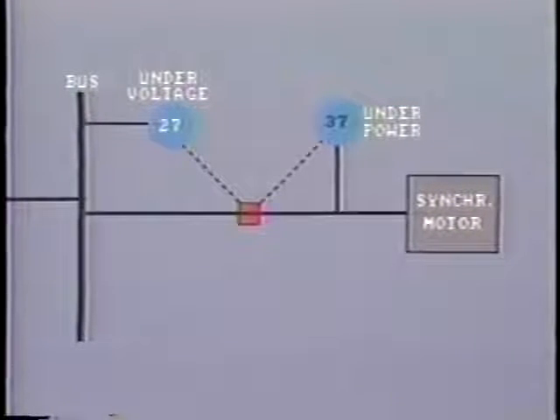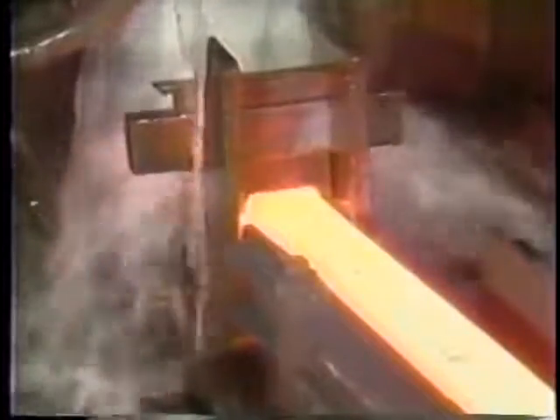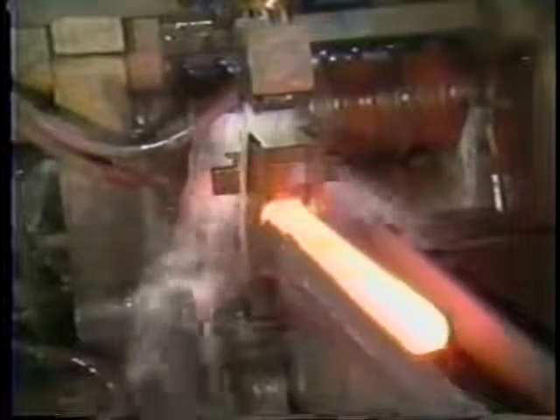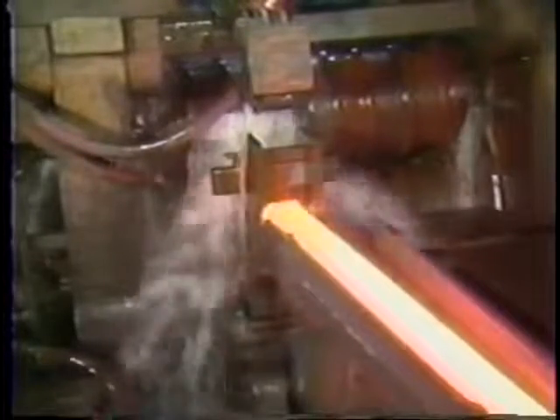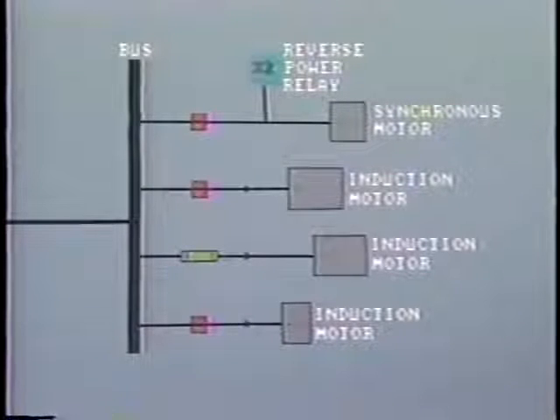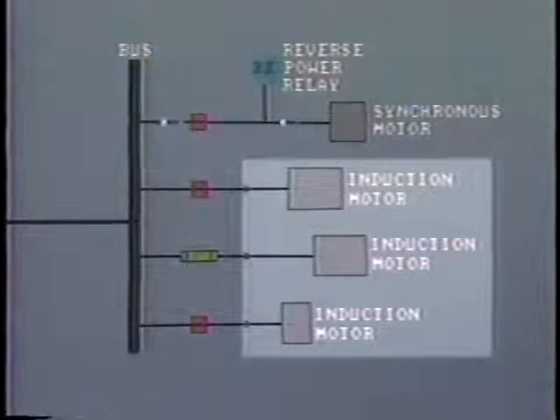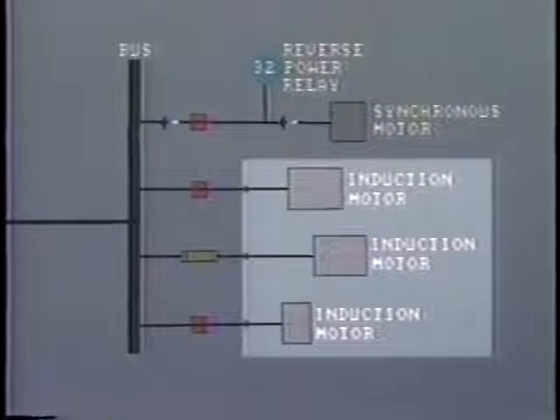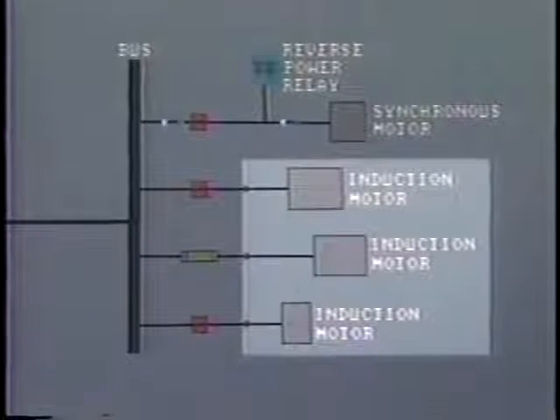This relay does have the disadvantage that it could trip if the driving machine suffered surges in power demand, such as in a steel rolling mill, for example. In this case, a reverse power relay, 32, would probably be installed. But this relay will only operate if the motor actually feeds power back into the bus. It can only do this if the bus is connected to other motors which can draw the power. In all probability, this would be the case, as most synchronous motors are used in large industrial installations.